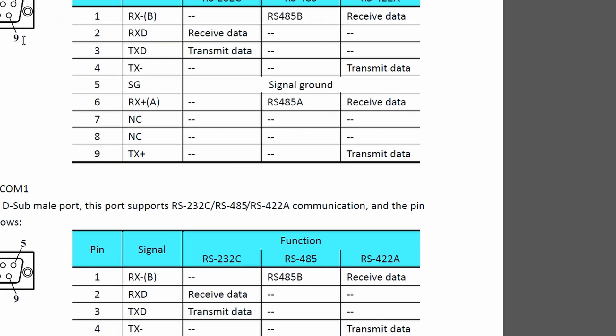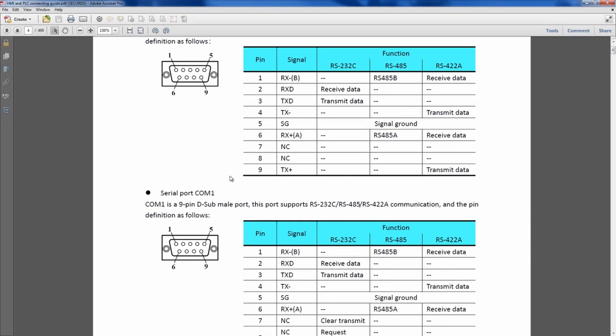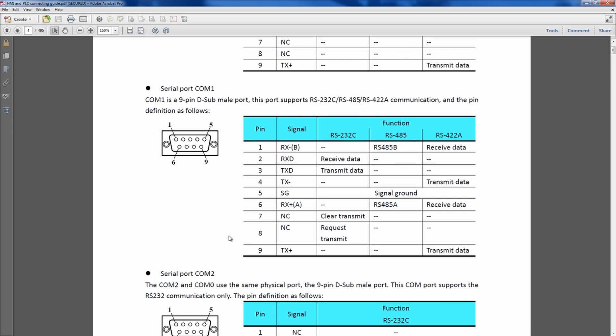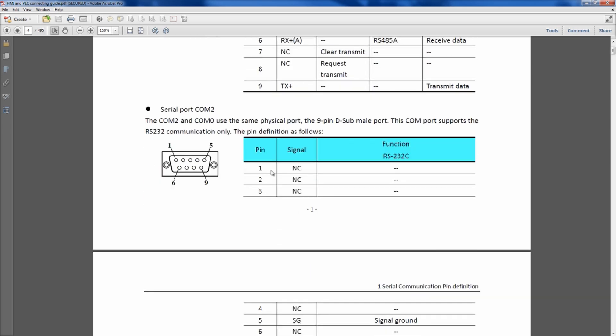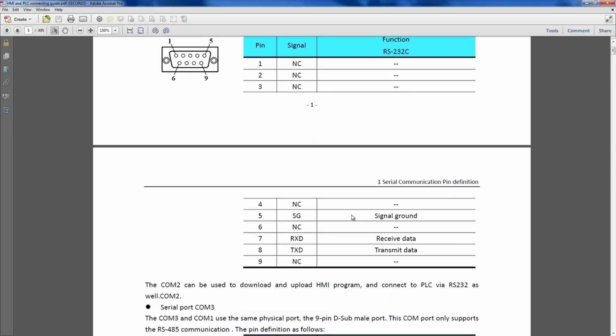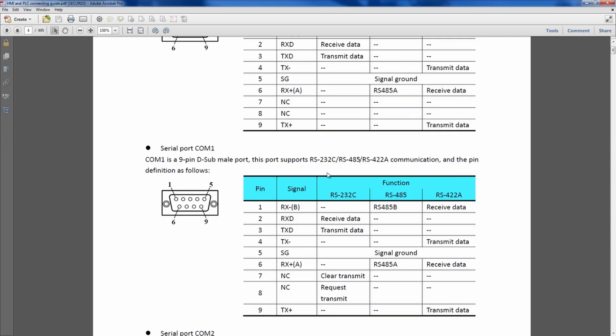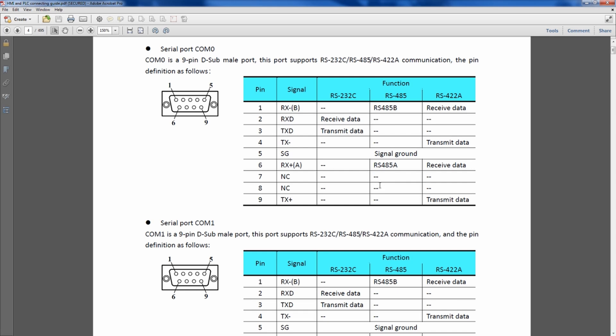If we take a look here, you'll see that every HMI is going to come with a COM0, COM2. It's actually the same D-sub pin. So whether you program the HMI to have a 232 on COM0, 485, 422, they'll have different pin definitions for you to transmit and receive data. You'll see here COM2 has nothing on pins 1 through 4, has the ground on 5, and has 7 and 8 for the receive and transmit. If you notice on COM0 up here, 7 and 8 in any instance is not used because it's used by the COM2. So they actually do share that same exact port.